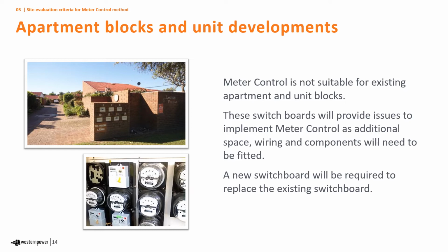And look, as with all these things, if you've got group meters, you've got a group main switch to provide wiring to the meter in the switchboard, you would need to do a whole of site disconnection to make the changes to the main switchboard. Quite often in these sites, you'll need a new switchboard to replace the existing switchboard.